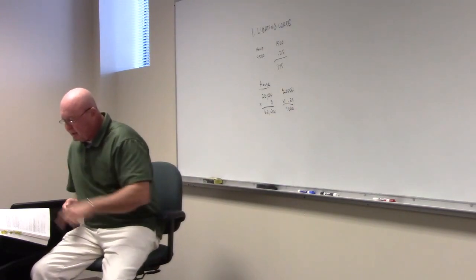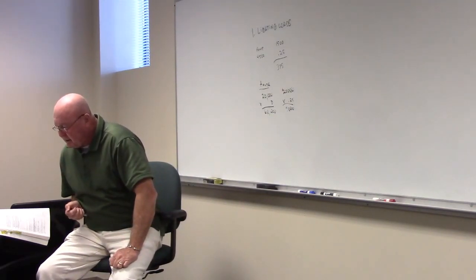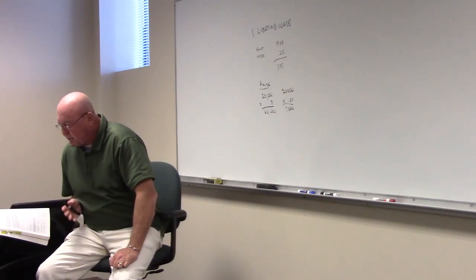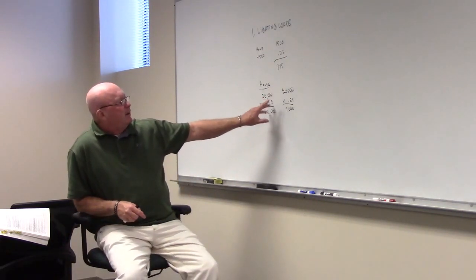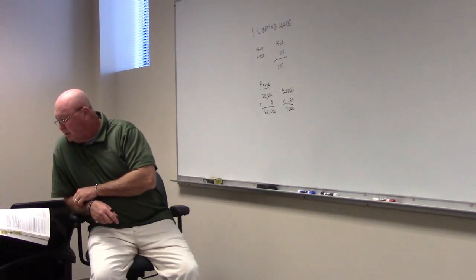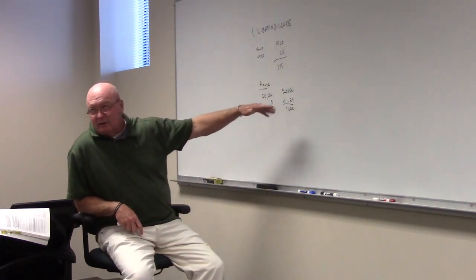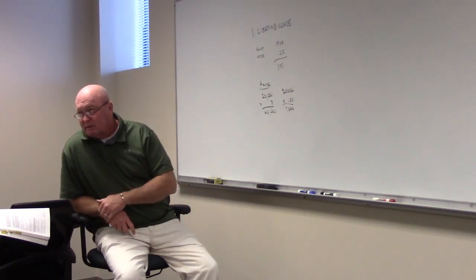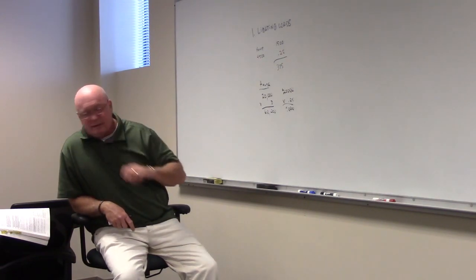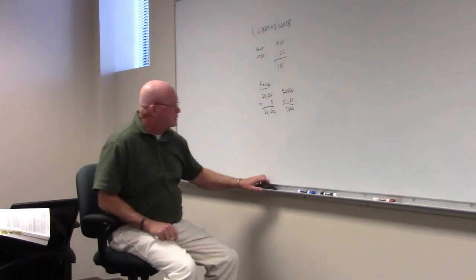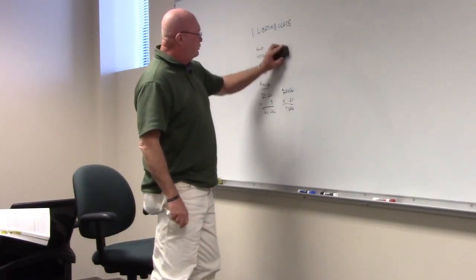So that's the first thing you've got to do there. And it gives some examples, and you see there the multiplication factor per square foot. Now I will say this much: in doing residential, there are some rules which we'll get to later. I'm not sure we'll get to them tonight. But there are some areas in the house that don't count for square foot. If it's not livable space, if it's not heated space, then it's not counted as square feet. But we're not going to talk about that right now. Number one is lighting loads.